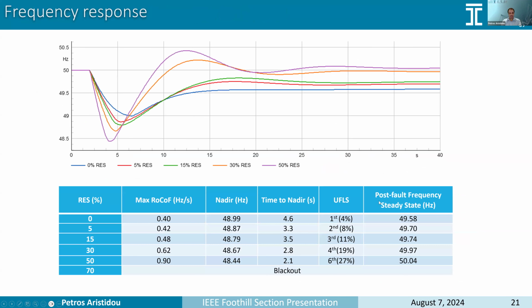So let's go to see what happens when we have a loss of a generator in the system. So these are 5 scenarios taken from different operating points, going from 0% penetration to 50% penetration. And as expected, we can see that when the renewable penetration increases, then the number of conventional generators connected to the grid decreases. And we have an increase in the maximum rate of change of frequency after the fault, going from 0.4 hertz per second to 0.9 hertz per second. But still, this is within the acceptable limits because we have a limit of 1.5 hertz per second. On the other hand, we can see that the nadir is very bad.